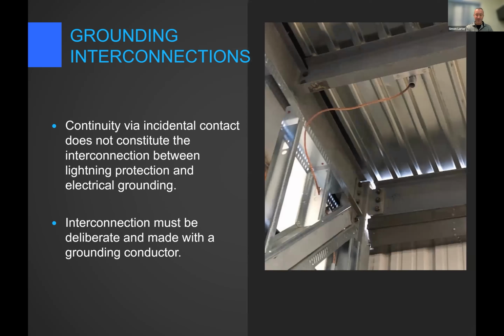And this is a question that I fielded just this past year, in April, I think, when the standard was issued. I'll pull that up a wee bit later on. This is a question I got earlier this year from an electrical inspector at a facility down in southern Alberta. He was worried that we had lightning protection coming through the roof, which we're allowed to do, and running down through the building. And I believe on the other side of that, cold form steel strut, we did have a conduit there, but to get to it, we looped kind of down, and there was some incidental contact between our lightning protection conductor and the steel.